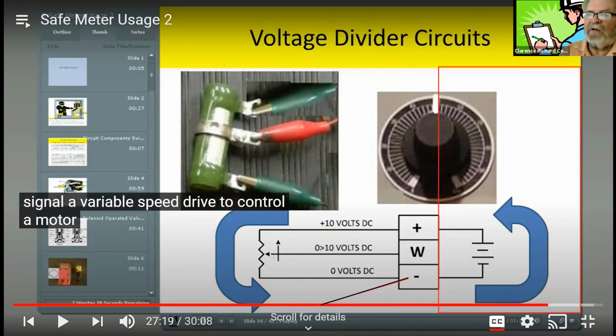What's happening here in that particular case, if you broke the wire right here, that means you're going to have 0 here, and this is like your filter right here. This 10 volts is going to build up all the way to where that break is. So if your wiper starts coming down here, it's still going to be reading that 10 volts, no matter where you put that wiper. So breaking that on the return side is going to cause that thing to go full speed, no matter where you put that wiper.